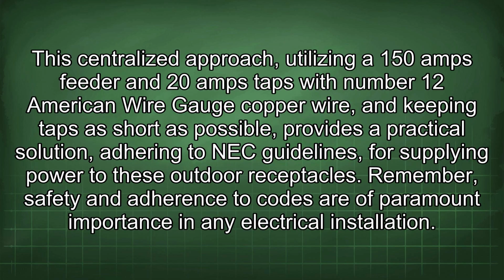This centralized approach, utilizing a 150 amp feeder and 20 amp taps with number 12 American Wire Gauge copper wire, and keeping taps as short as possible, provides a practical solution, adhering to NEC guidelines for supplying power to these outdoor receptacles. Remember, safety and adherence to codes are of paramount importance in any electrical installation.